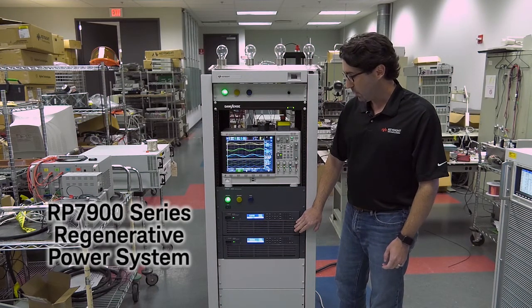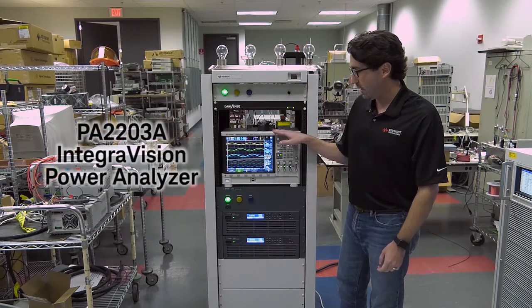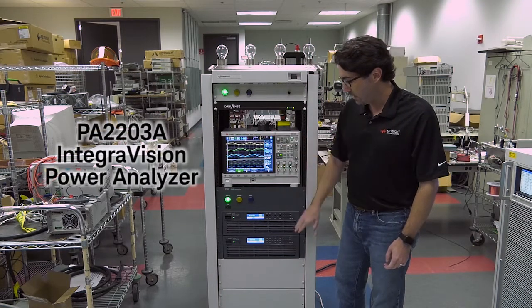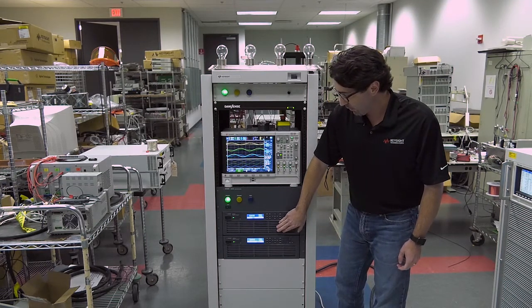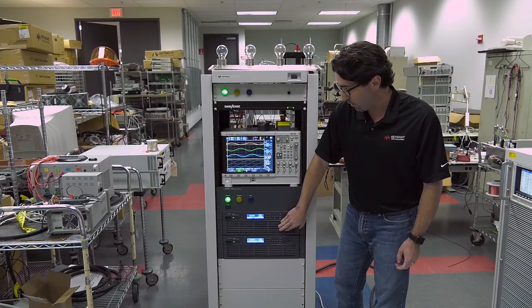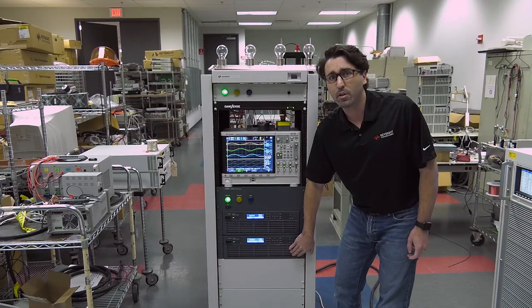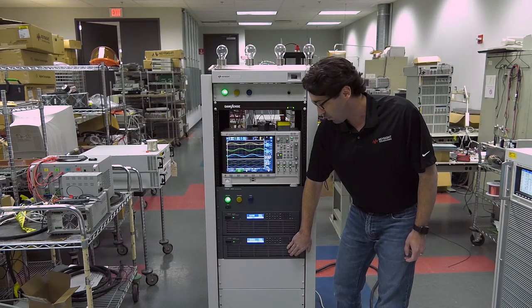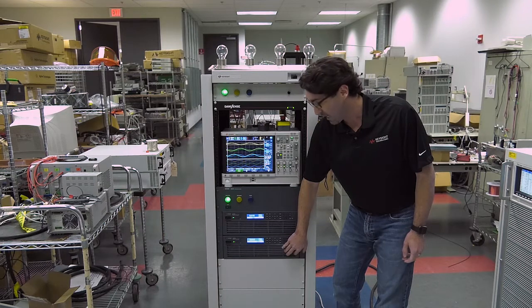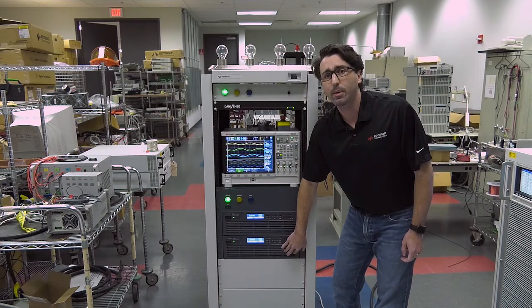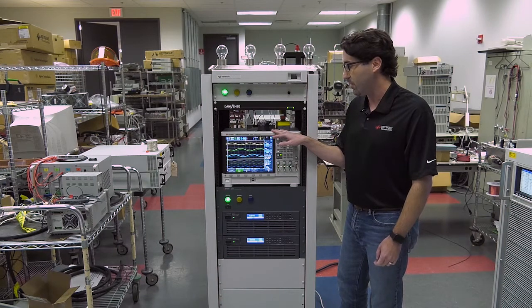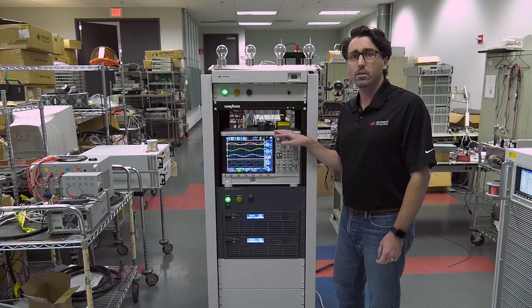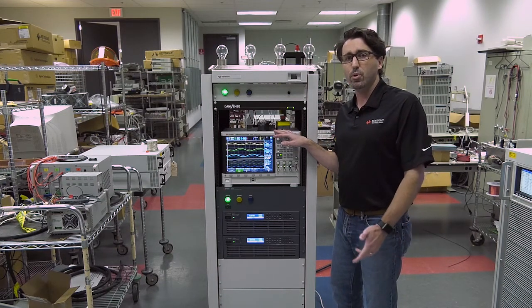What we're going to do is use the power analyzer to measure how cleanly we regenerate power back to the grid. The top regenerative power system will be sourcing power into the bottom regenerative power system, and that one will be taking that power and regenerating it back to the grid. We're going to use the power analyzer to measure the total harmonic distortion of that regeneration to show you how clean that is.